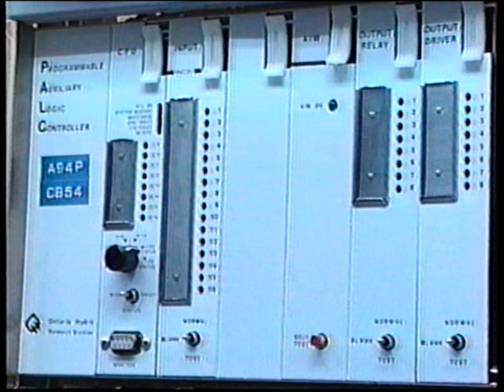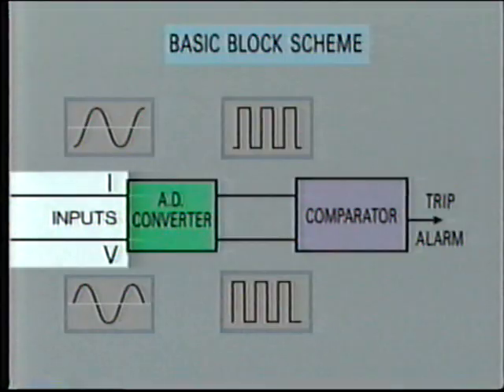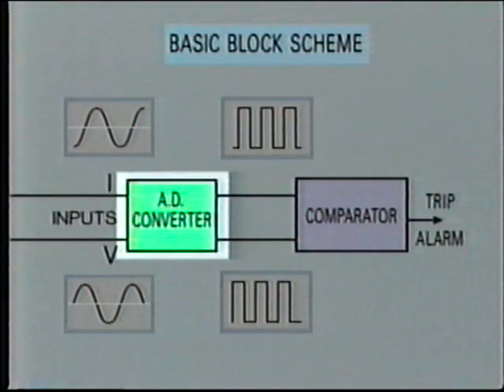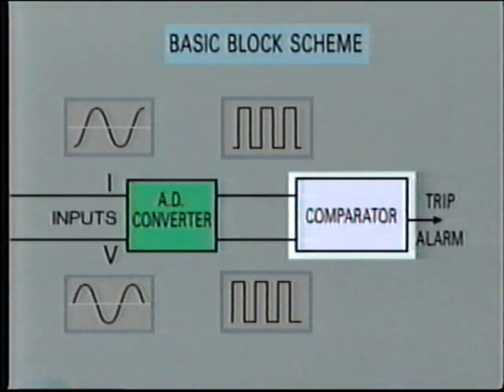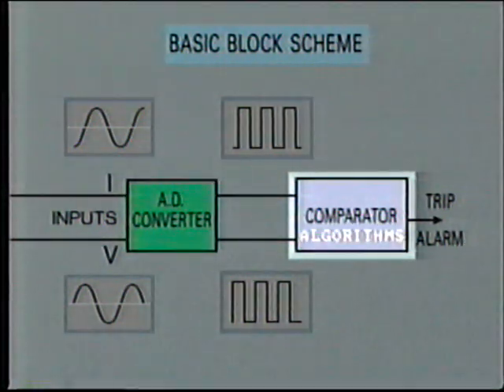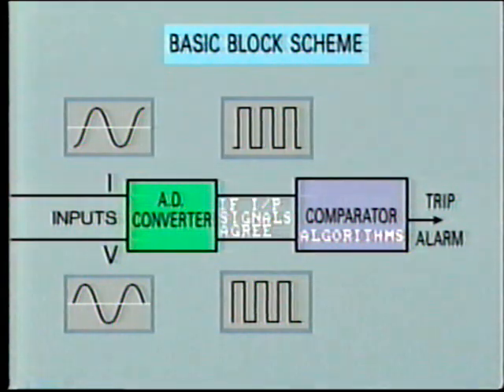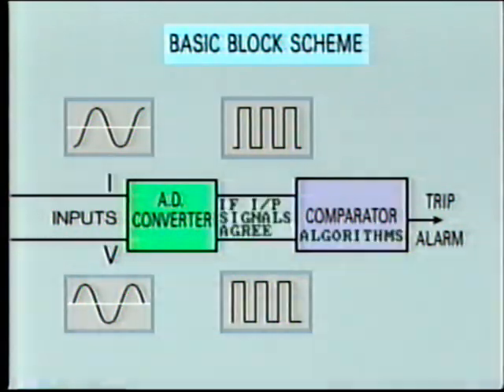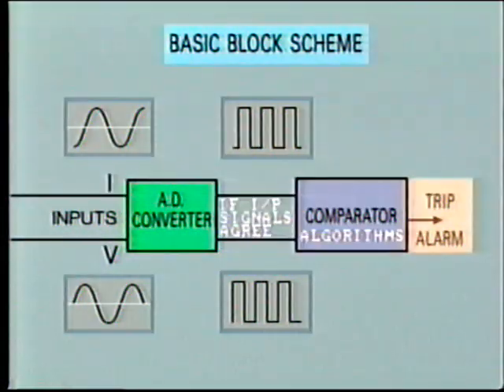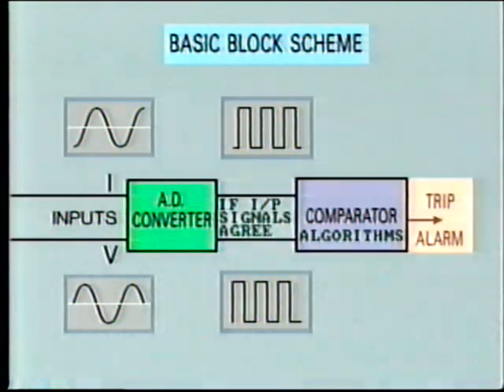Both of these conditions can be improved by the use of microprocessor relays. In essence, the incoming voltage and current signals are converted to digital format and then compared with the reference values, algorithms, which are already stored in the computer. If the incoming signals agree with all of the conditions imposed by the microprocessor's algorithms, the relay will provide an output signal to either trip, alarm, or perform some other action.